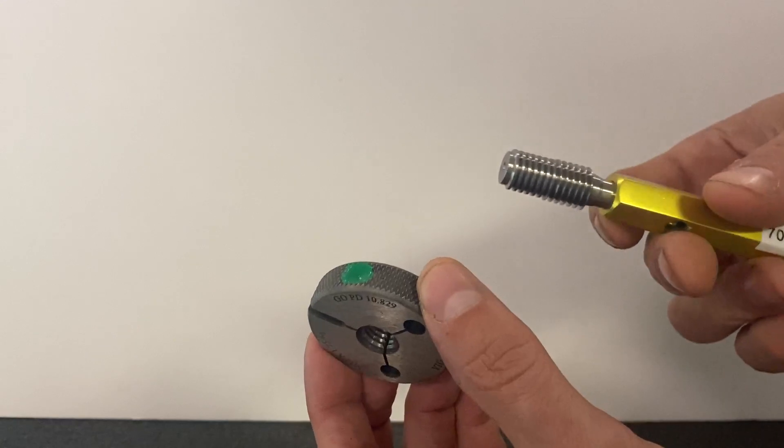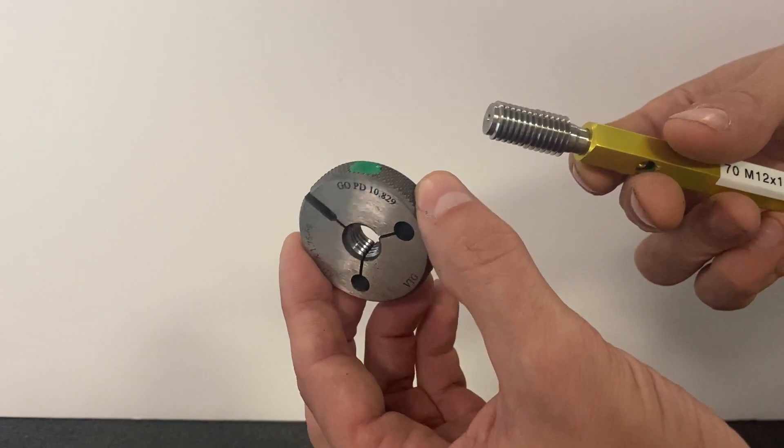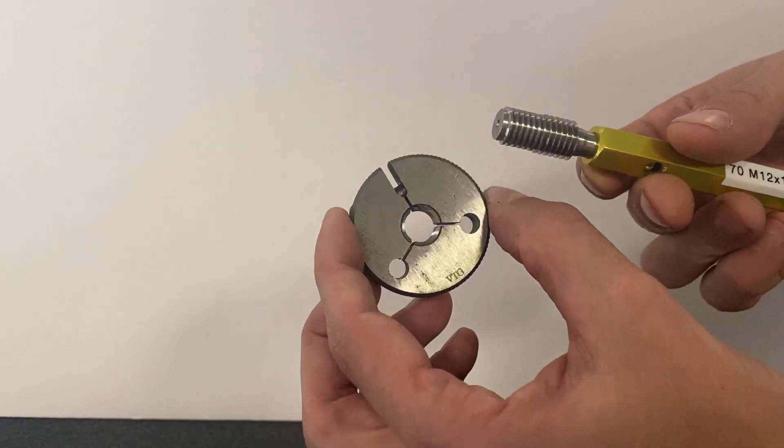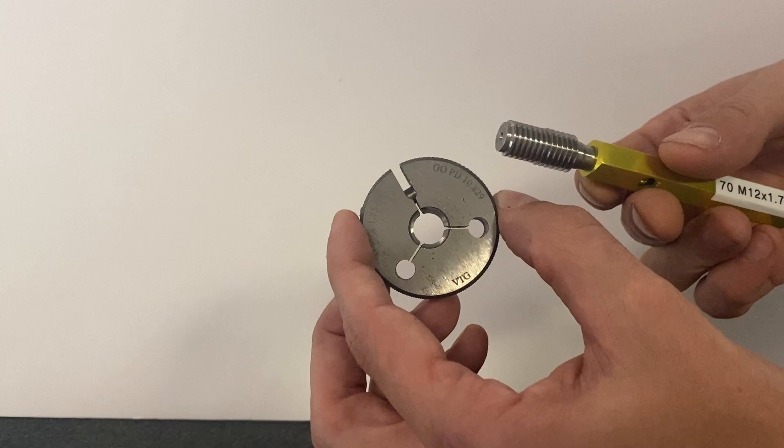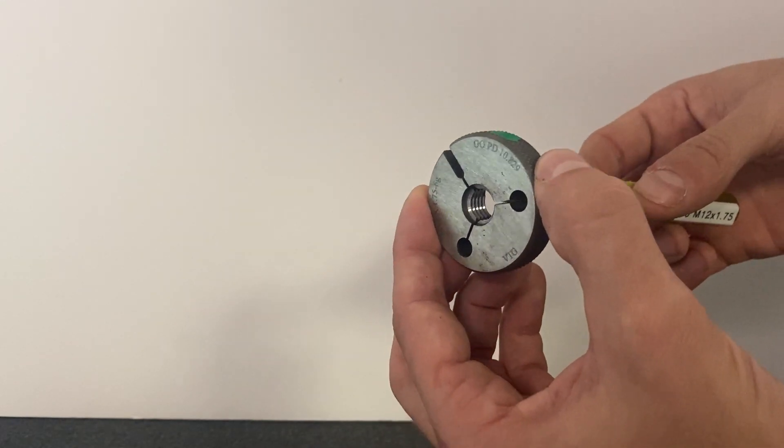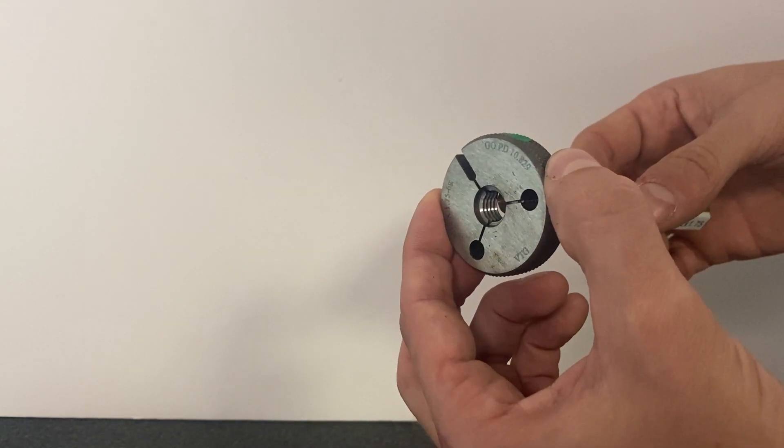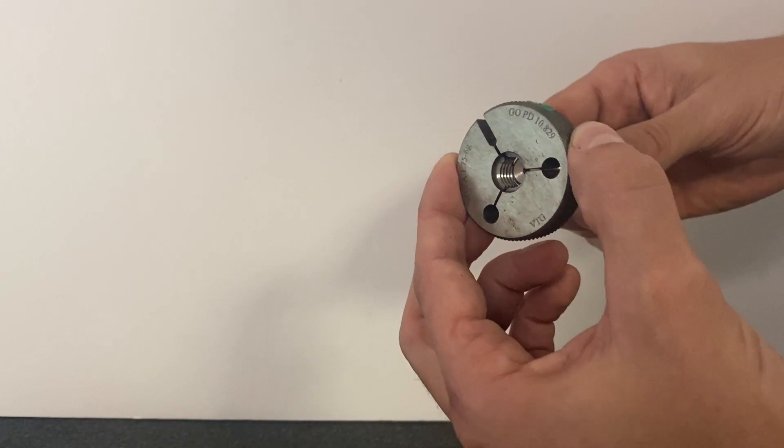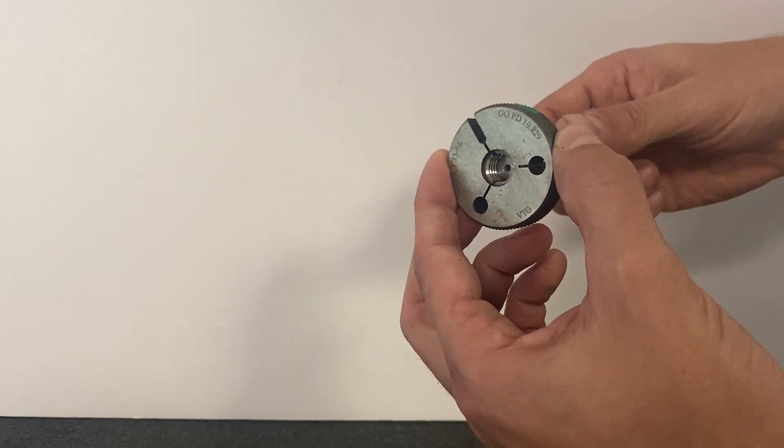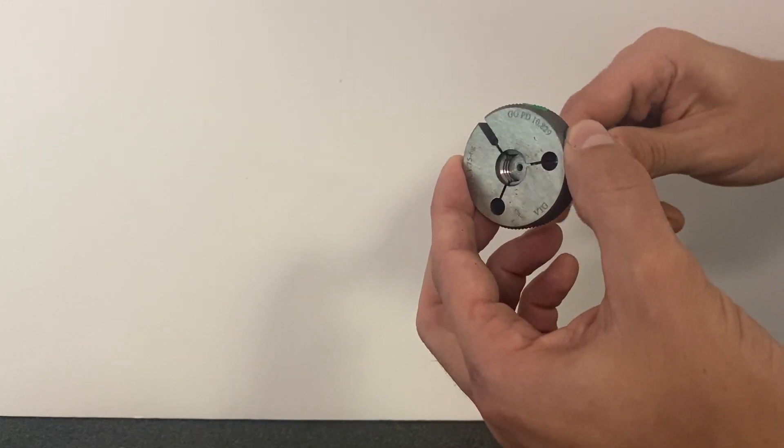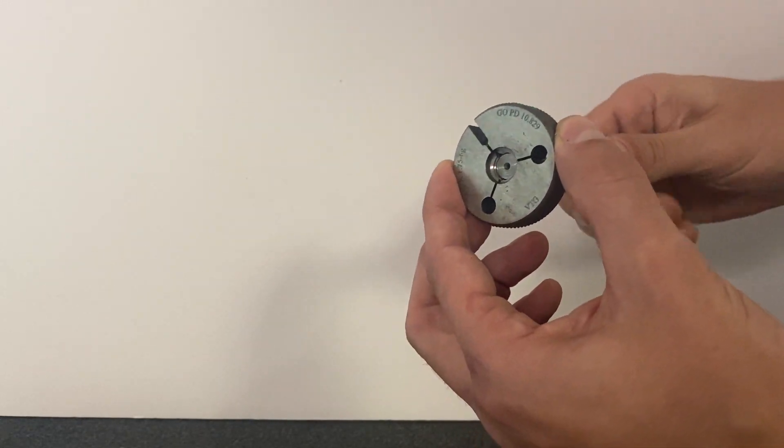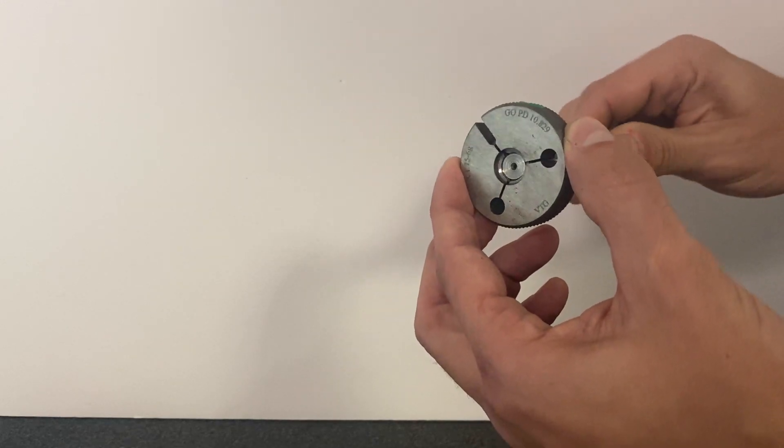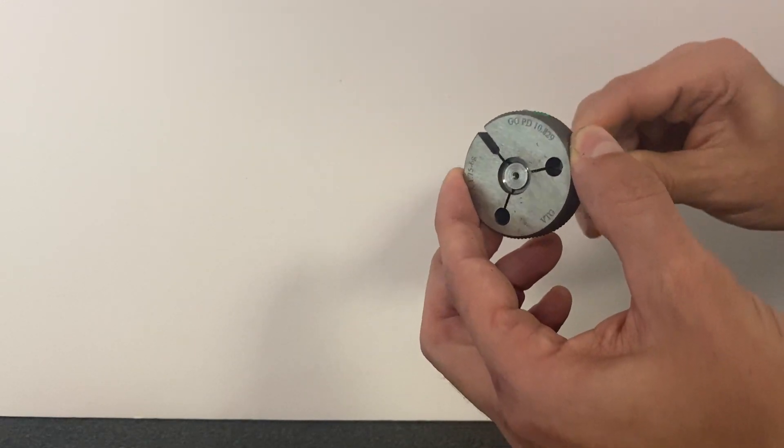You use the calibrated thread plug to set the adjustable thread ring. You do that by feel, so it's kind of hard to demo in a video, but you thread the gauge in and you should begin to feel it grab and provide a little bit of friction.